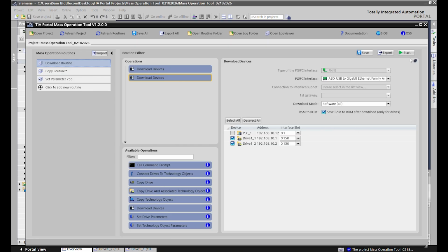And then from here, you would just click start and you would go through the process. And so going back to our VFD workshop that we run, at this point, we would have all the drives configured, we would have the parameters set, we would have them commissioned, but now there is an obstacle that comes up where our I/O board control, specifically the potentiometer analog input, is defaulted to a bipolar input, -10 to +10 volts. However, the way we have our demo unit set up, it has to be unipolar, 0 to +10 volts.